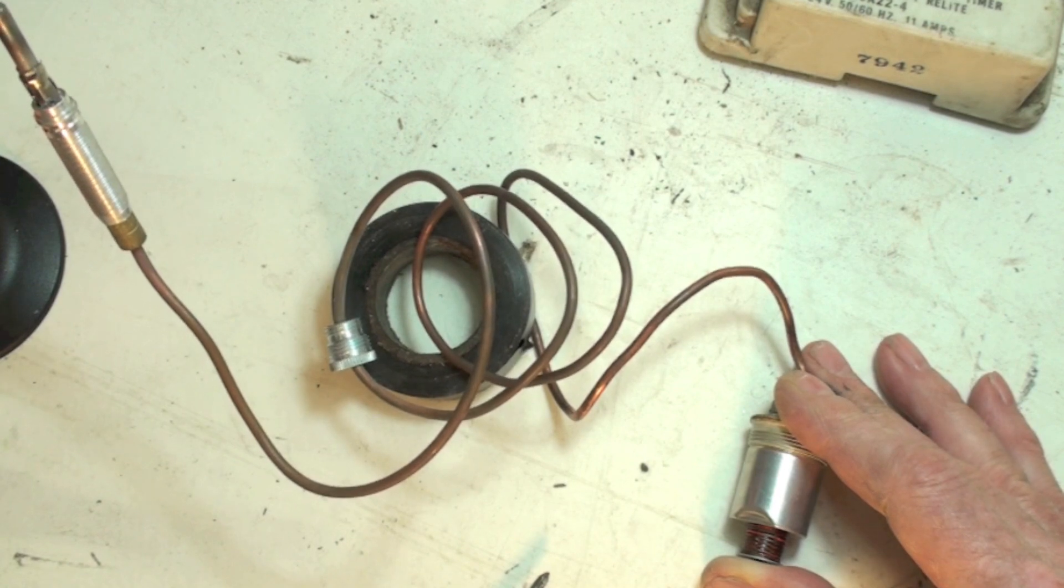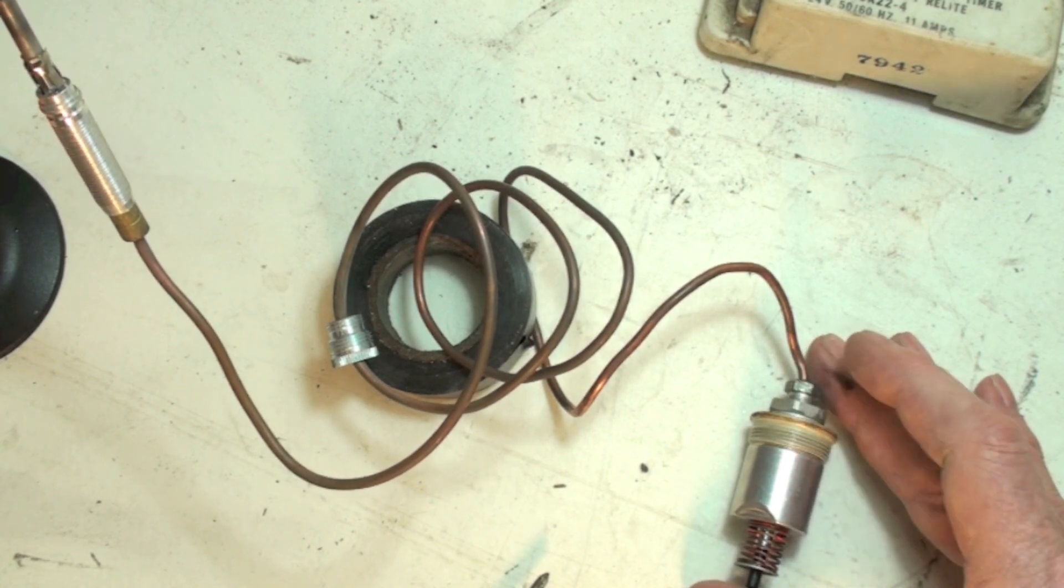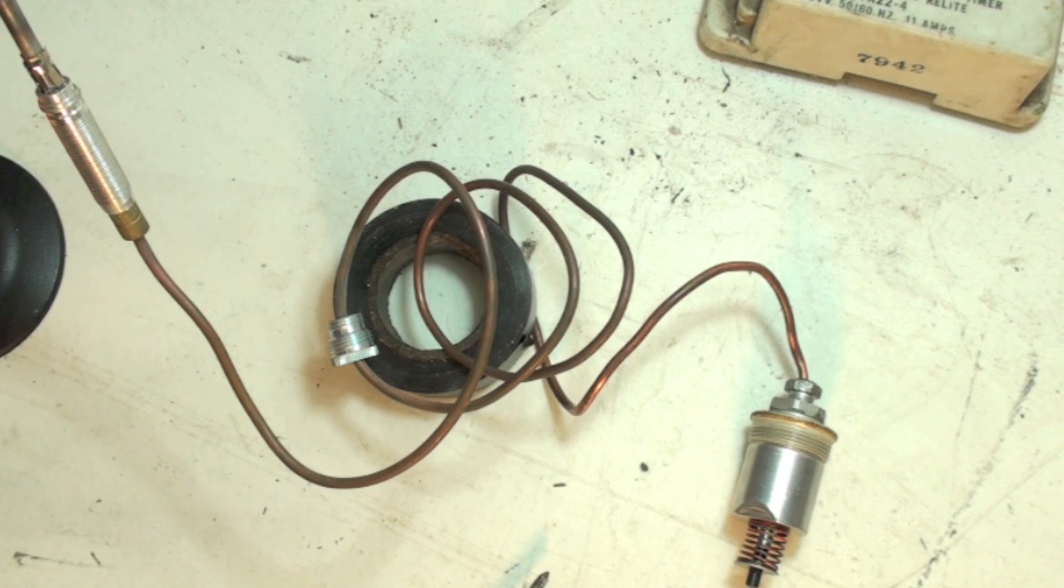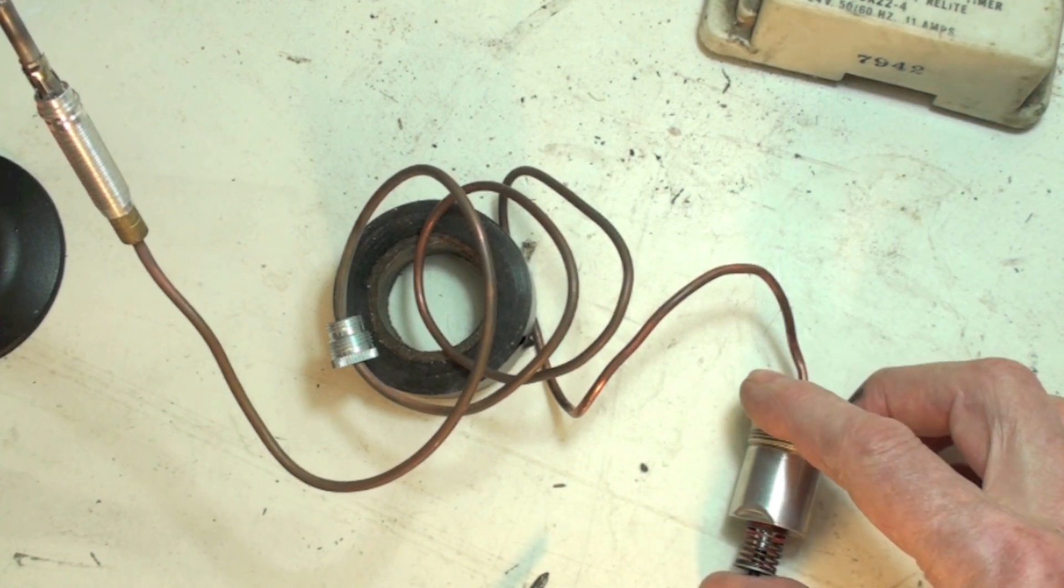As long as there's heat from the thermocouple, it's going to work. When the heat from the thermocouple is gone, it's going to drop out. Now I've got an artificial heat source here, which is just a little torch. Now it's warming it. Now I'm going to come over here, and I'm going to hold this up.